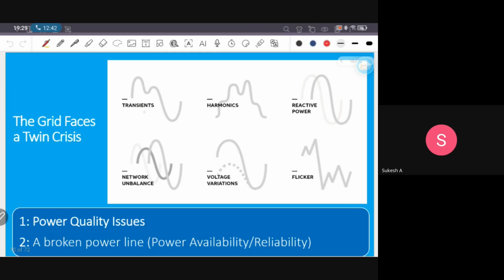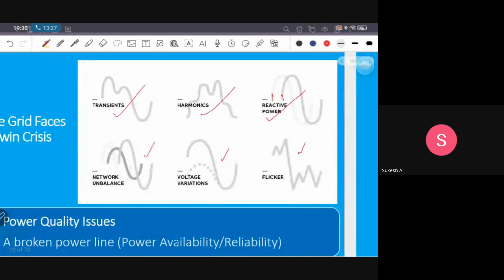Transients happen over a very small duration, and harmonics can last for a very long duration. Reactive power is not a direct power quality issue, but the phase difference will cause a huge amount of current to pass through our distribution network and cause heating. Network unbalance again causes circulating current in our machines, and voltage variations cause malfunction of consumer equipment. And flicker directly affects our lighting loads and sensitive electronic gadgets and equipment.